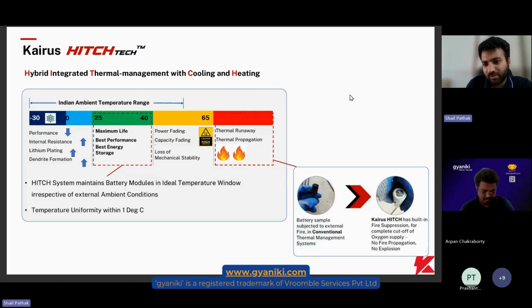You can see a small image on the right hand side, which shows the fire safety aspect. We did a test where two cells were subjected to external fire. One battery system was incorporated with the Hitch tech and one without. The one without, when given external fire, was completely destroyed in less than 3 minutes. But the one with Kairus Hitch tech sustained for 50 minutes, and after that it vented out, but did not have any explosion.